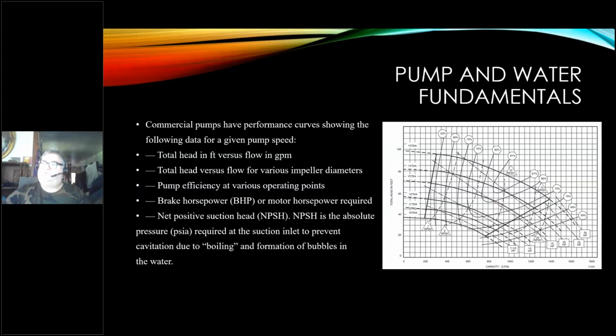In a closed system, in other words, pump the water around the pipes through the coils, chiller, and back to the pump. You push out a gallon of water, it comes back a gallon the other side, unless you have a restriction somewhere that chokes off the water getting back. And if that restriction works through the entire system, it will starve or negate the effect of the pump. Right? So that's something to watch for. But you'll see where you're at on this pump curve. That's something that you don't get when you just walk up to the pump.